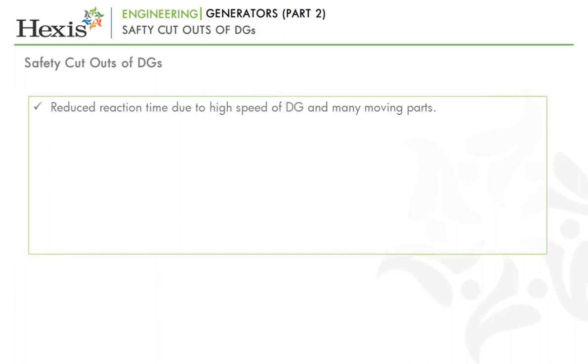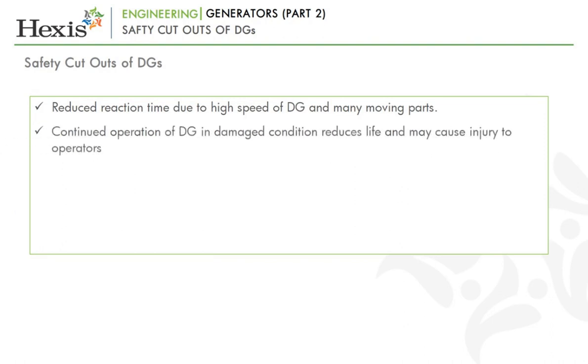Let's now look at some of the safety features of DGs. With multiple systems and elements working in tandem in a diesel generator, there are too many things that may go wrong with any of the systems and at a speed which may not give adequate reaction time to the personnel manning the system. Continuing operation of a DG in such conditions can damage the DG to a large extent and also cause unsafe conditions for personnel in the area.